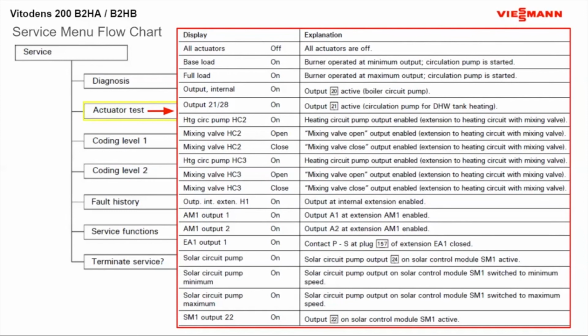Because with Lambda Pro, when it first initially starts, it first checks itself at really lean, meaning we're giving it way too much air than it needs. It checks its flame sensor reading there. Goes to what they call Lambda, which is perfect combustion, checks itself there, and then goes to really rich, meaning now we're giving not enough air to the boiler, and it checks itself there with its flame sensor reading. Then once it does that, it goes back to Lambda, or a little 1.3 of excess air. Then it's good for you to put your analyzer in the boiler, because if you do it when it's going through a really rich, your analyzer is going to go through the roof. So just remember that during your full load and on your base load, make sure that it's already up and running before you throw your analyzer in there.